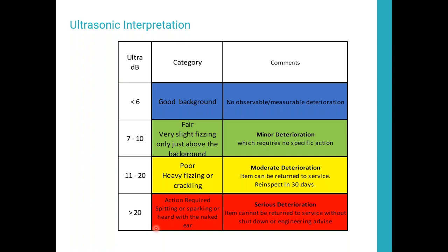And it may have had the same reading that would have existed when that gap that was the size of a pencil was 4 inches wide still. So you can't tell by amplitude how much time is related or how much time I have till failure, because there's no way to really determine how much insulation material I have left. Visual inspections, that's what's going to give you an idea of how bad it is and how much time you have based on the physical damage done to it. So that's one of the limitations we have.